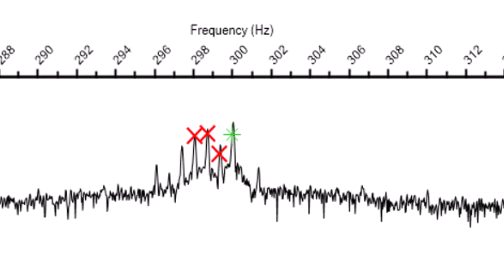And this fifth harmonic is, as you know, for 4 poles and greater, a key evolution in the determination or verification of a rotor anomaly. We always say correlate—make sure you have multiple data points pointing in the same direction.